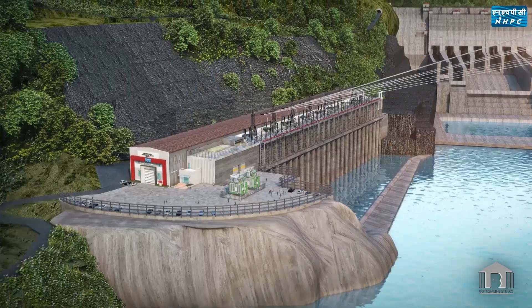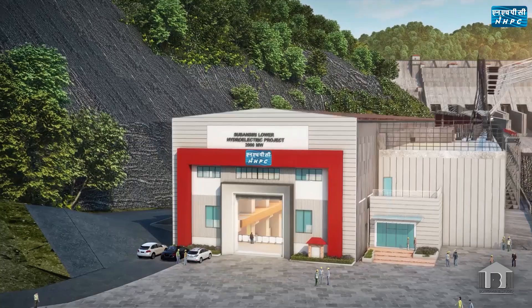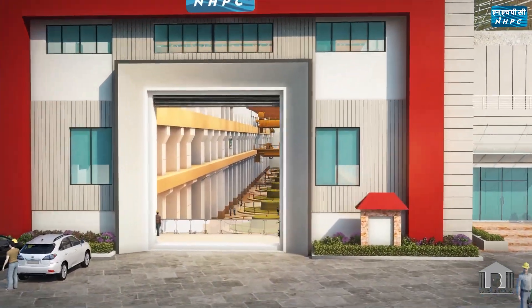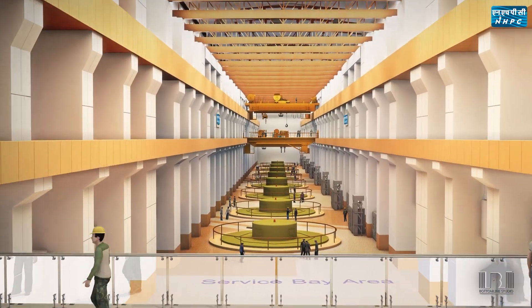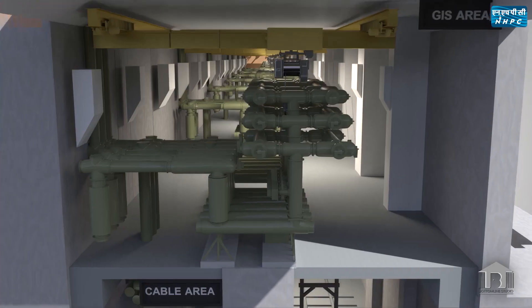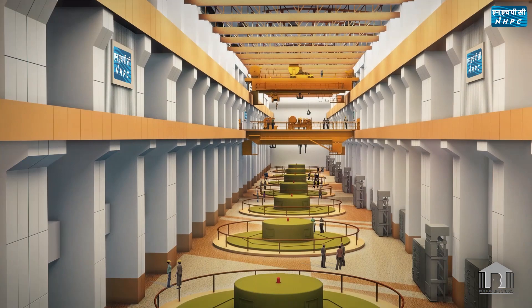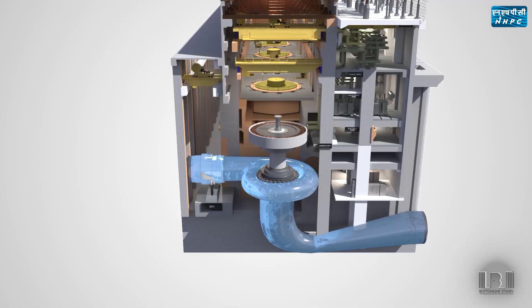The surface powerhouse of the Subansiri Lower Project is located on the right bank of river Subansiri. The powerhouse is designed to house eight 250-megawatt machines, transformer bay, GIS block, and pothead yard. The auxiliary building, transformer bay, GIS, and pothead yard are located downstream of the main machine hall. To isolate the machine from the water conductor system, a MIV has been provided upstream just adjacent to the machine hall.